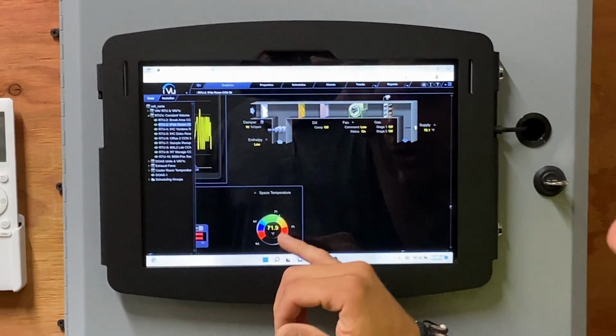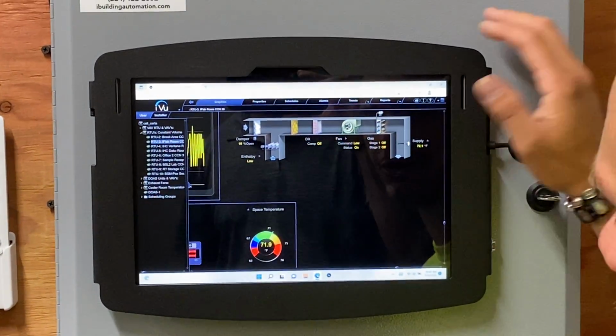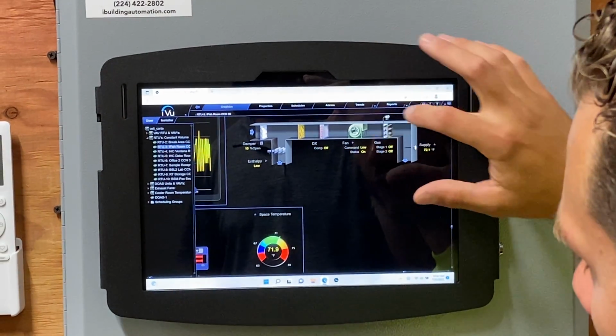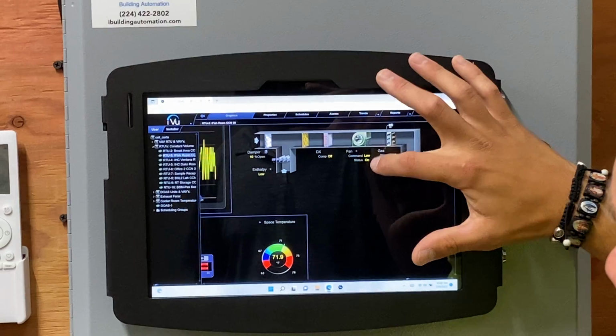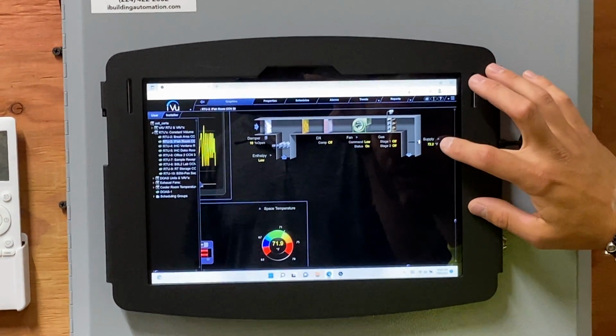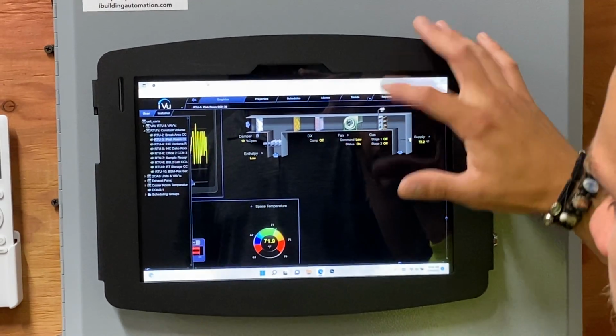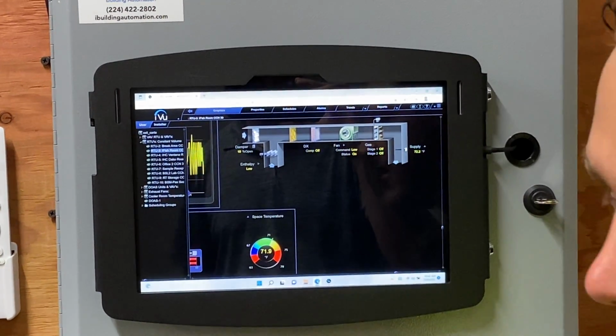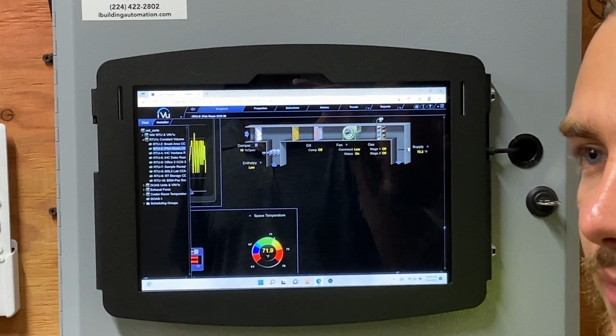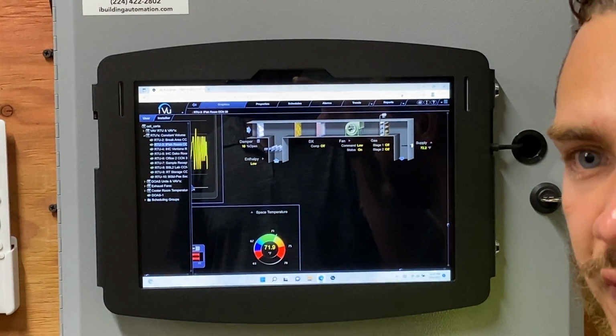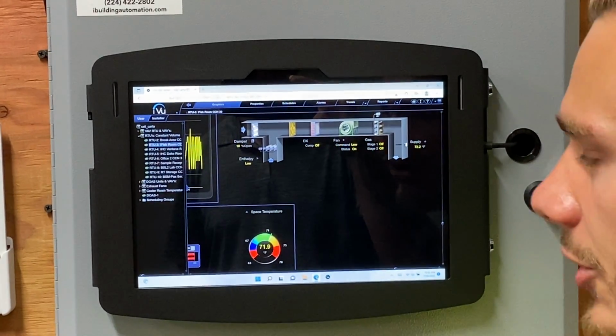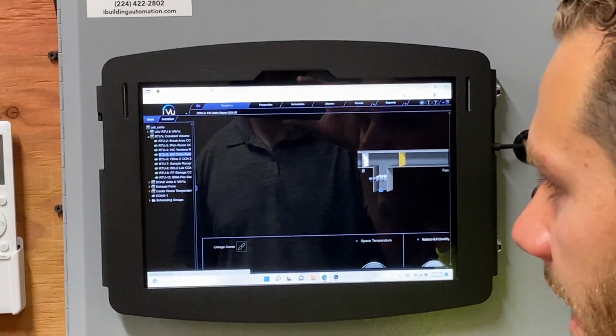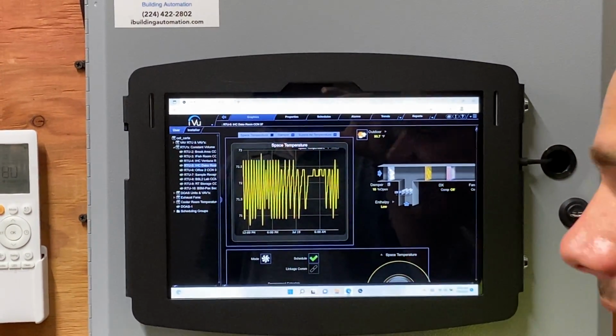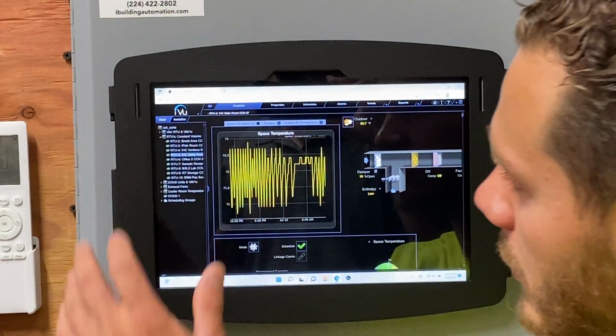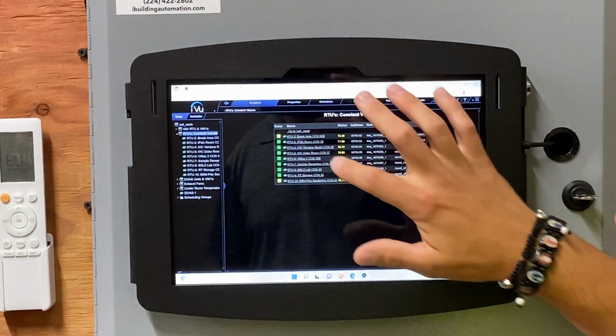You have your space temperature here, which you'll want to reference, and as your rooftop comes up, again you want to check your fan status first. Fan command is low right now, it's on, then the supply air temperature based off what you need, gas, and again your damper percentage, which will be the same for all units until an air balancer wants to change it, or you guys feel 10% is too much. The rooftops are all going to be the exact same.